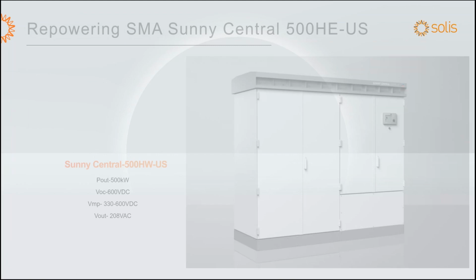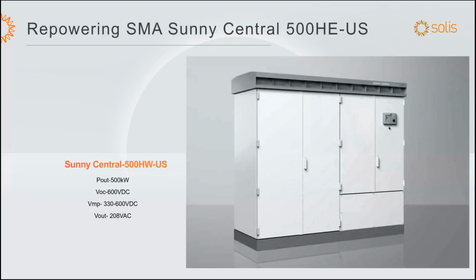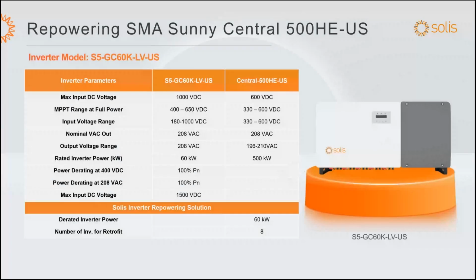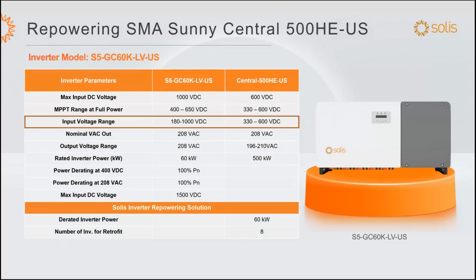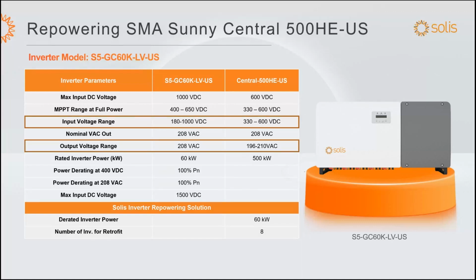SMA 500, similar approach, but this one is a 208 volt AC. And that's where we're using our 60 kilowatt low voltage inverter. So at 208, we can meet the input voltage range with this inverter. It's rated 180 to 1000. And we can meet the output voltage range. So this inverter could meet exactly the output voltage range of the SMA inverter. And it will take 8 inverters to replace a 500 kilowatt SMA inverter.